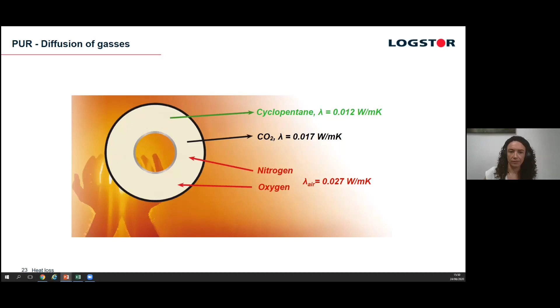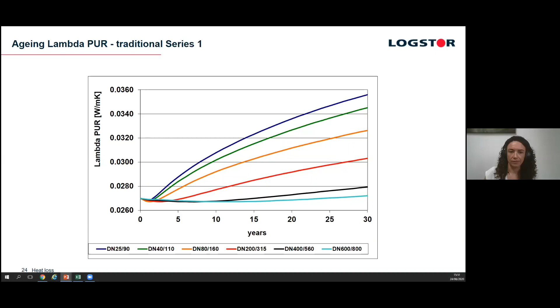If you look here at the aging curve for traditional Series 1, look at the smaller sizes - that's a massive difference. Particularly DN25, DN40, DN80, you're losing a huge amount of those high insulating gases over time. Much less so as you get to higher dimensions, such as 600 diameter.